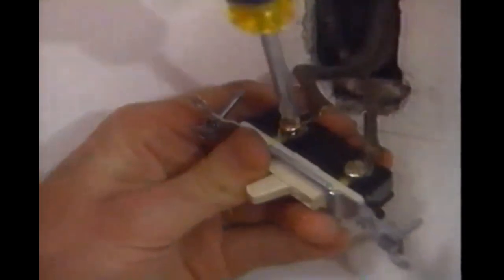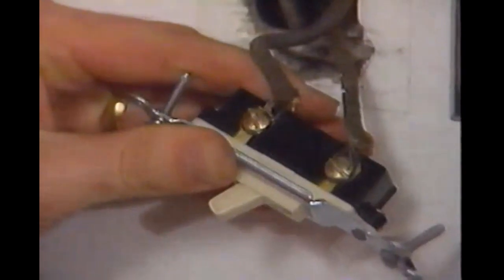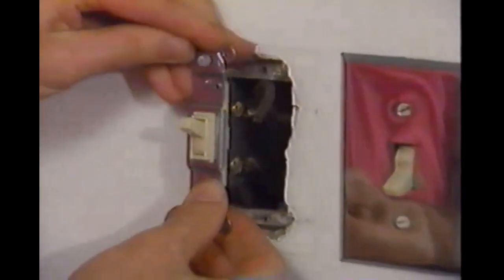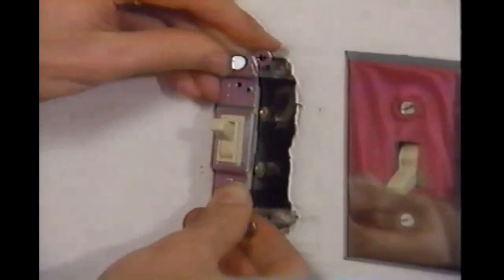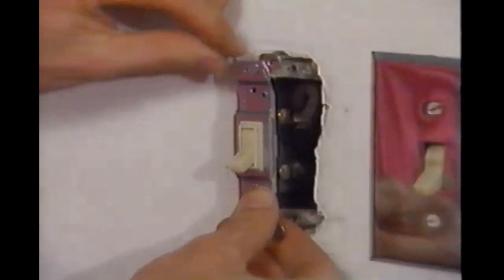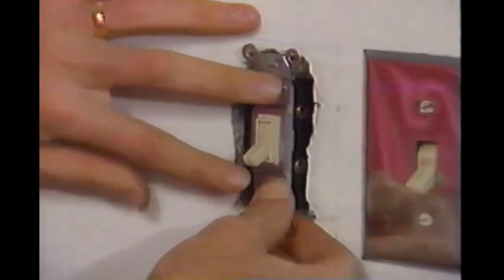If your wires are already stripped and formed, hook the wires around the screws clockwise and tighten them. Before inserting the switch into the box, push the ground wires to one side, then fold in the neutral wires, followed by the switch. Never force it. Fasten the mounting screws, replace the cover, and tighten the screws.